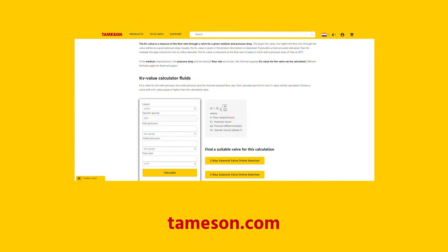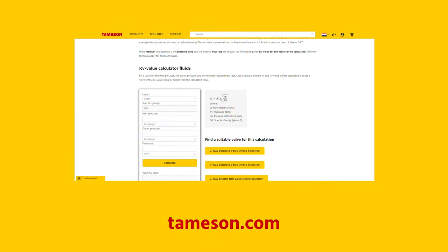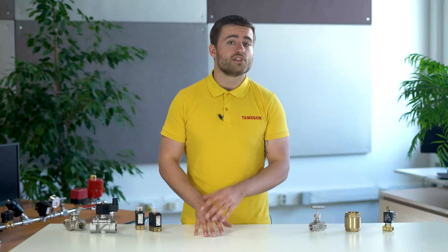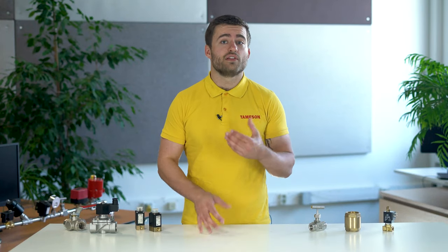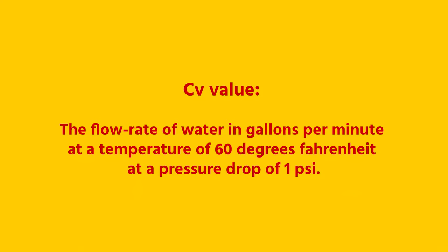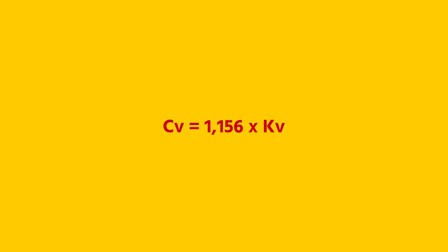You can calculate the KV value with our calculator on Tameson.com. Countries that use the imperial system use a slightly different value, the CV value. The CV value is defined as the flow rate of water in gallons per minute at a temperature of 60 degrees Fahrenheit and a pressure drop of 1 psi. The KV and CV values are related as follows: CV is approximately 1.15 times the KV.